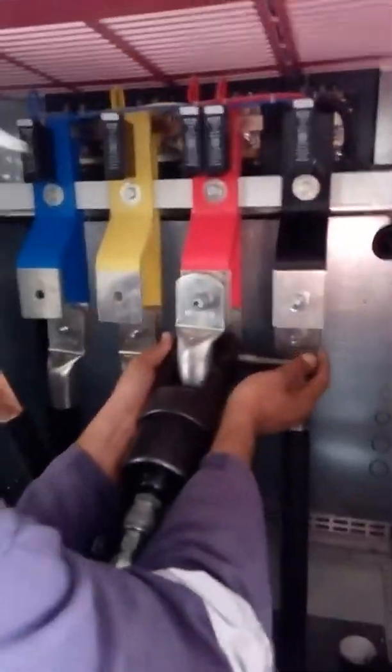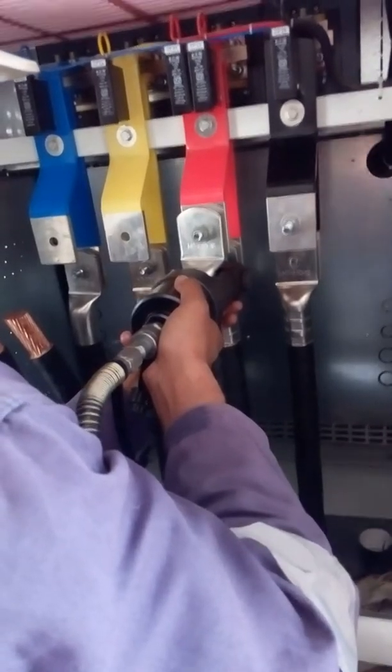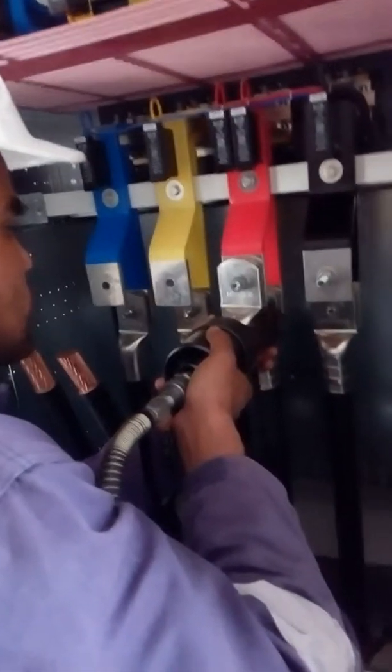Our main concern here is using the hydraulic tool. This cable is going to the generator. Now already — Salahuddin gave order. It means starting to pump. First need to check the alignment. Same like this one, you need to put your nut and washer temporarily so 100% our hole of the lugs and the terminal for the Main Distribution Board align. You see the terminal from here and this one, and also from the lugs.